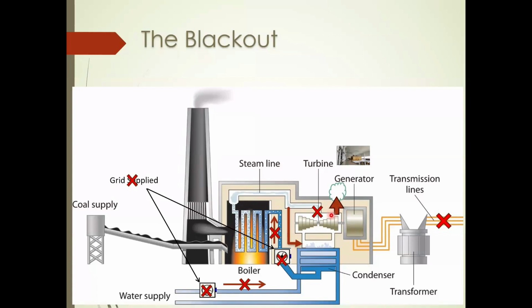So in order to resume operations, you have to close this rupture disc or replace it. It's very hard to replace this one because simply more steam is being pumped out. Steam is being exhausted here, so you cannot reach this particular place without getting to the safety limit. So it takes about 2 to 3 days minimum to reach this place to replace this ruptured diaphragm. Now I have prepared a video for you, so you can look at how the rupture disc exhaustion happens during a blackout.